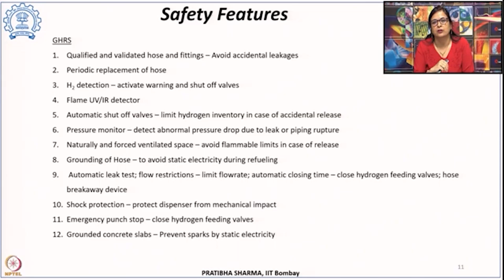These hoses are grounded so as to avoid any static electricity which could be generated during refueling. Automatic leak testing, flow restrictions and automatic closing times are included, so as to not only limit the flow rate but also to close the feeding valves, and hose breakaway devices are present. Then there is shock protection to protect the dispenser from mechanical impact, and emergency push stops to close the hydrogen feeding valves. These slabs are grounded so as to avoid any sparks from static electricity.